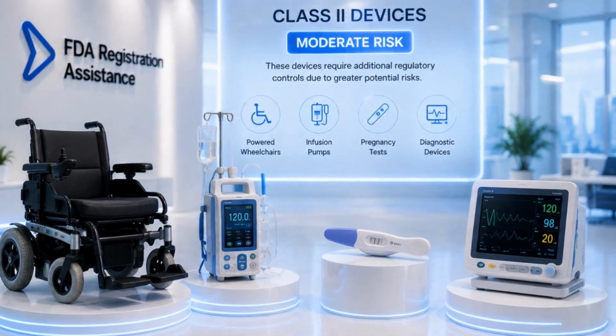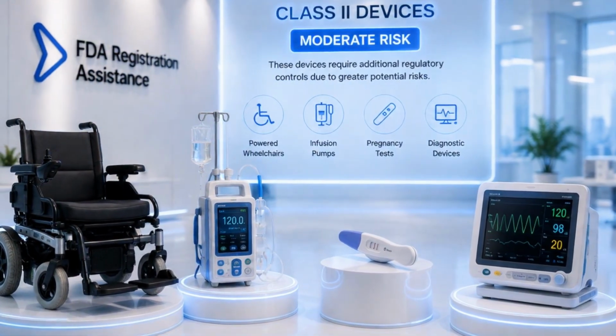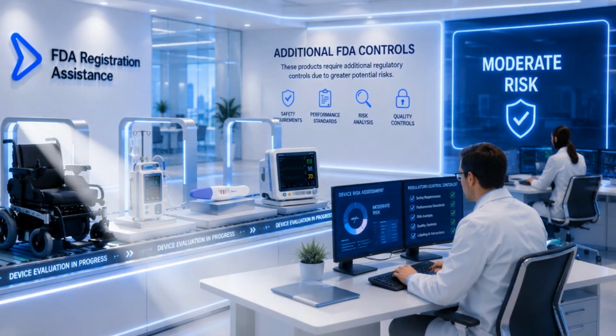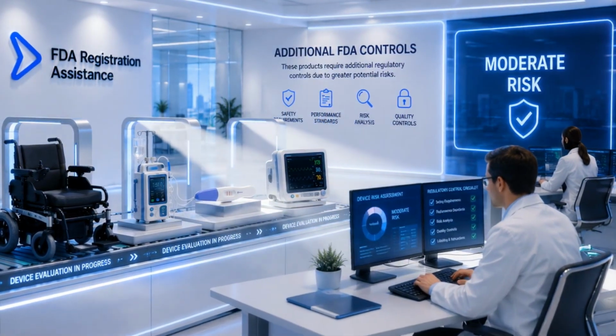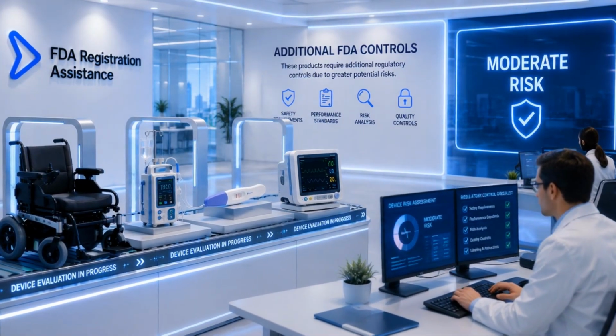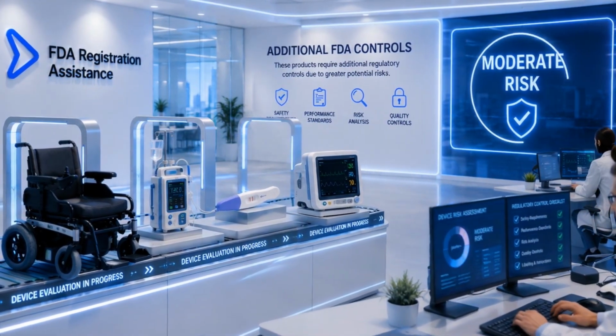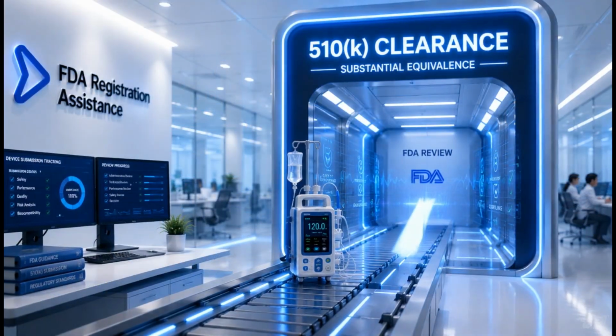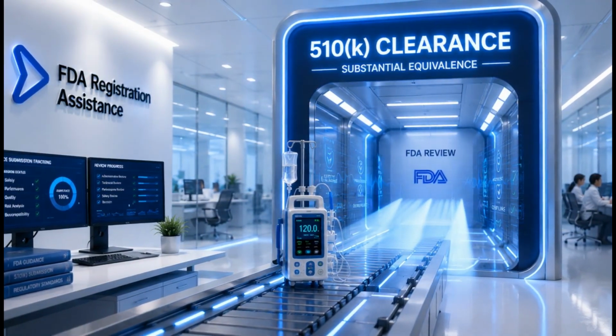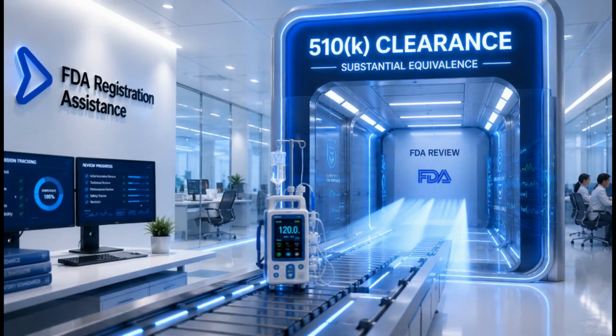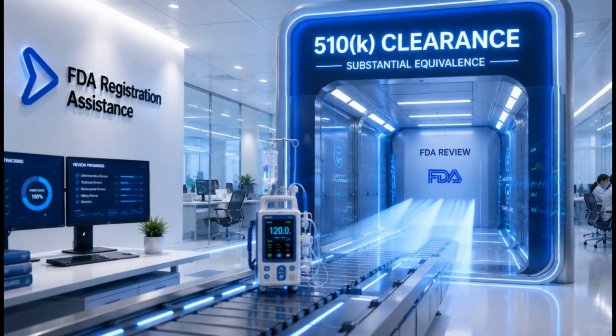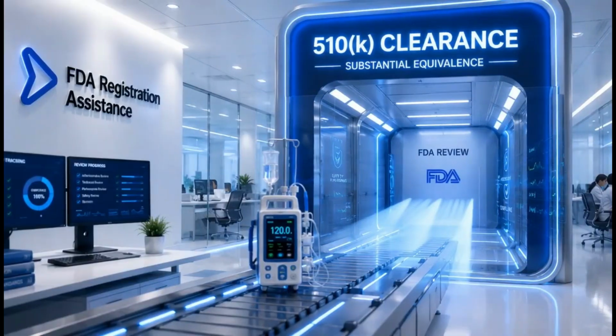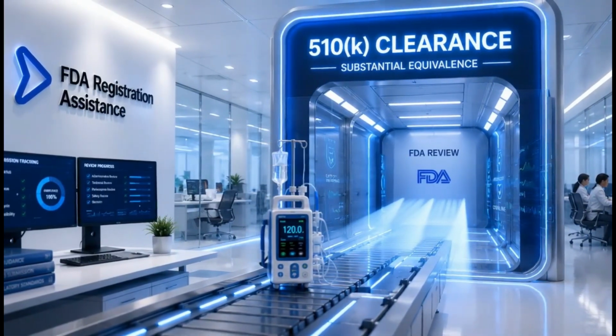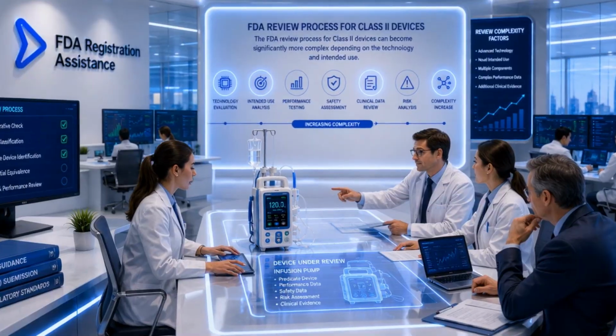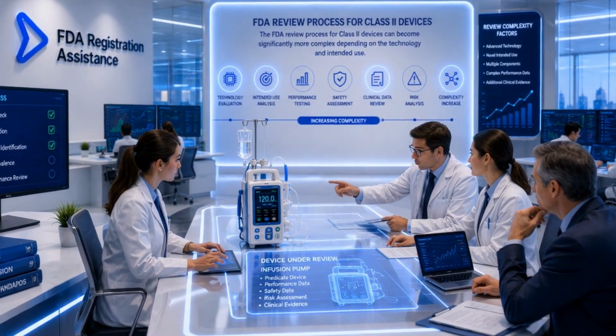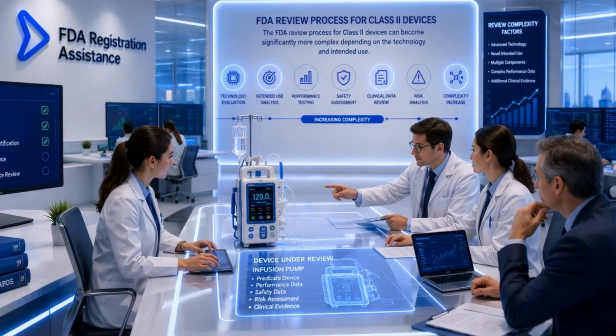Class 2 devices are considered moderate-risk medical devices. These products typically require additional regulatory controls because they present greater potential risks to patients. Examples can include powered wheelchairs, infusion pumps, diagnostic testing devices, pregnancy tests, and many electronic medical products. Most Class 2 devices require FDA 510(k) clearance before they can legally be marketed in the United States. A 510(k) submission is designed to demonstrate that the device is substantially equivalent to an existing legally marketed device. The FDA review process for Class 2 devices can become significantly more complex depending on the technology and intended use.